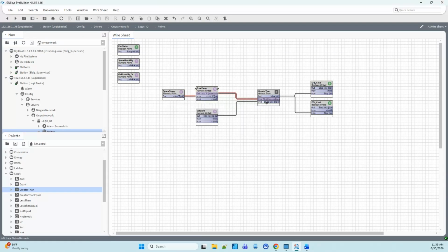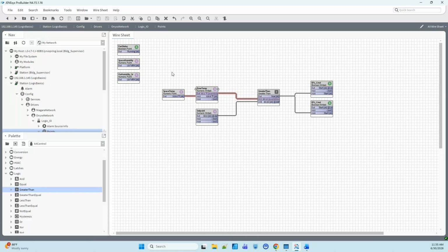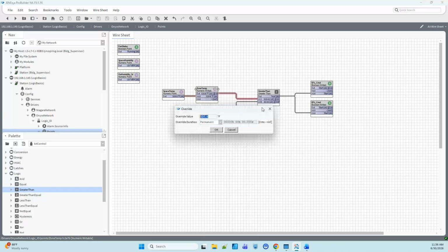I actually just heard the click in the back of my lab there. So we'll do that, and oh, I actually do have some inputs there. I guess I did set them up. You saw that this went to 326, so it went completely closed. It sees that the sensor is shorted out. So I do have them there in the back. I didn't think I had anything wired to that controller, which is kind of funny. But regardless, even if I put this back to auto now, we should see that temperature decrease. Actually, we won't because it's still closed. So we'll say 70 again, and we'll turn everything off there.